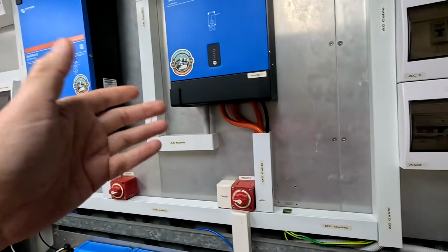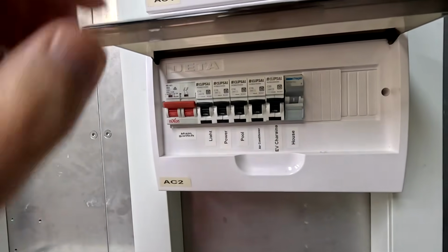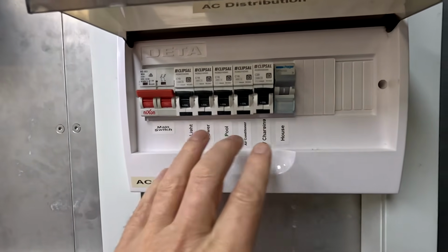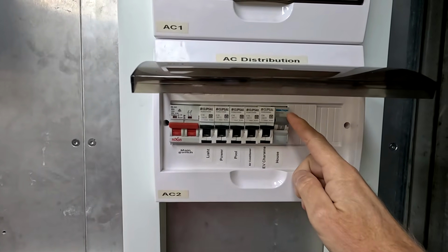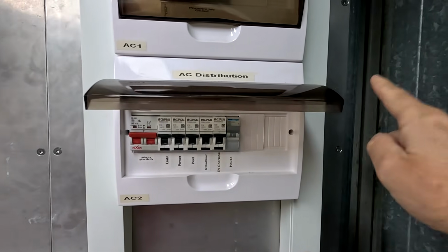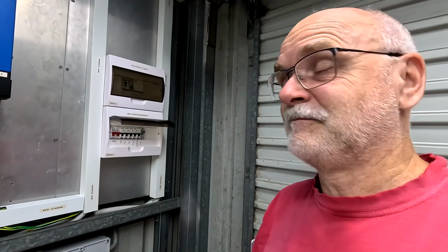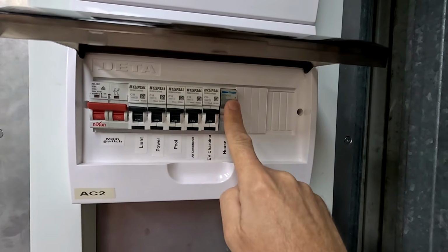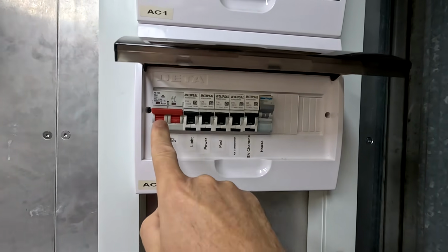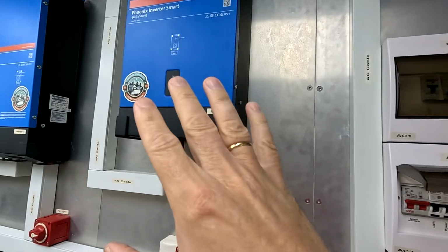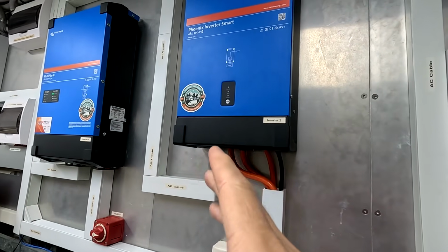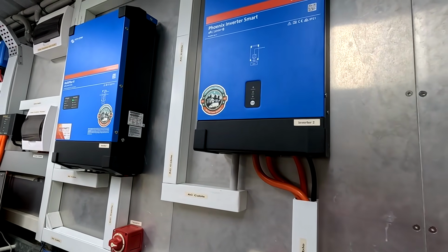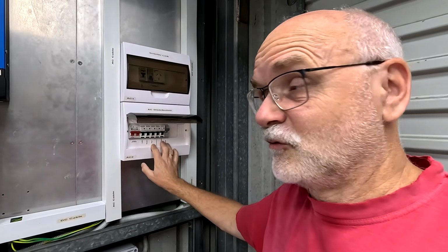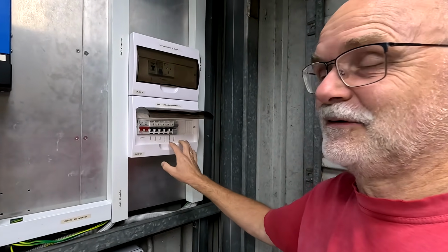So in here inside the battery and system room, we have now the house circuit connected. I can either disconnect the house circuit from here, from the outside meter box, or from inside the house with the main switch as well. This is a 50 amp circuit breaker here for the house. Even the Multiplus and the Phoenix will produce only 33 amps maximum, but this has all been done to future-proof this installation, this upgrade.